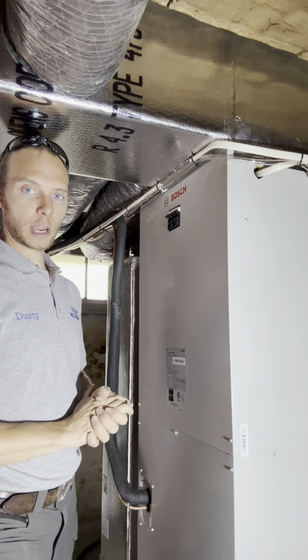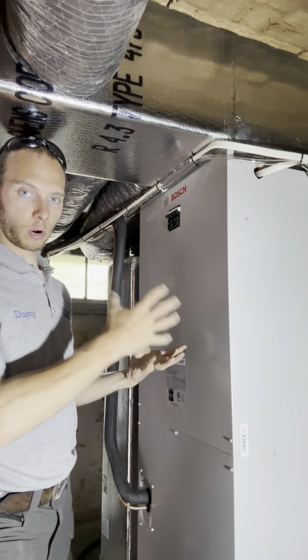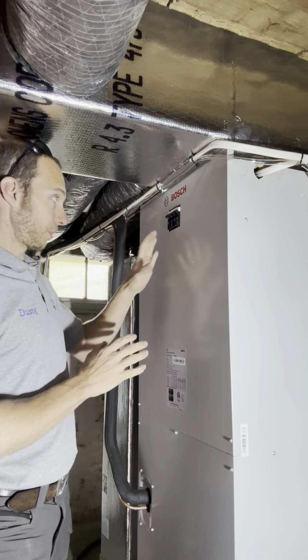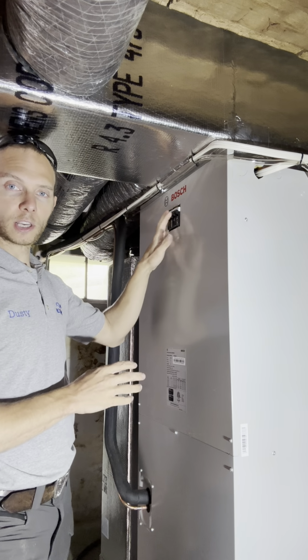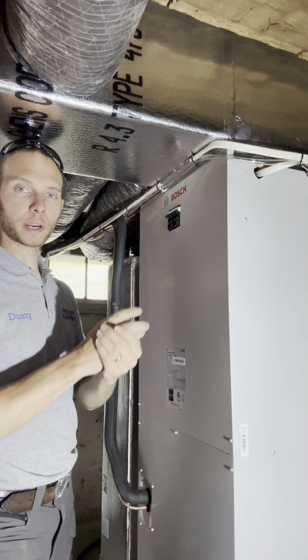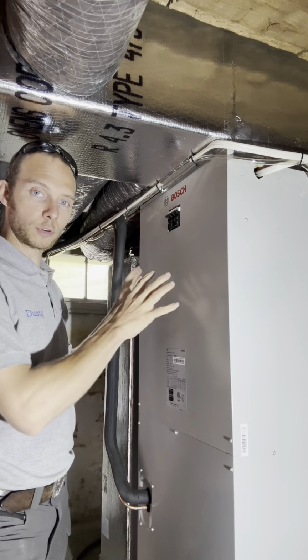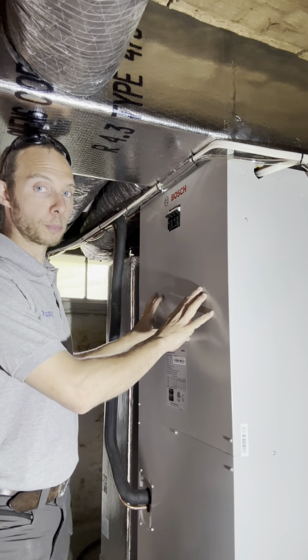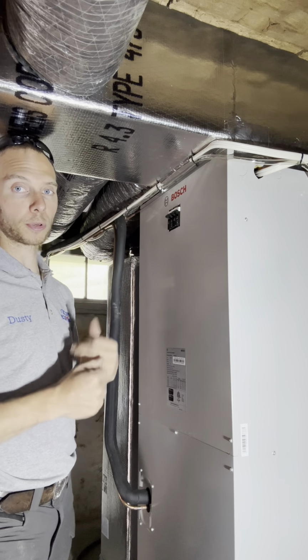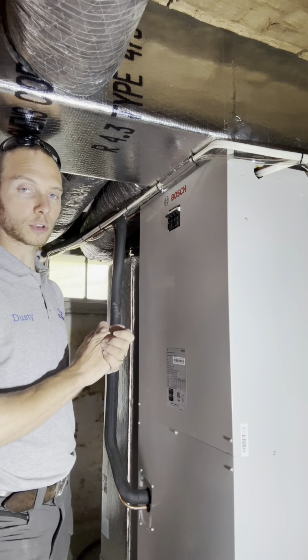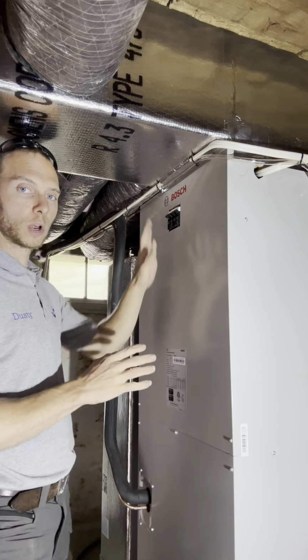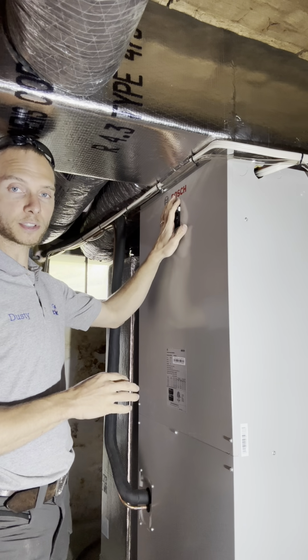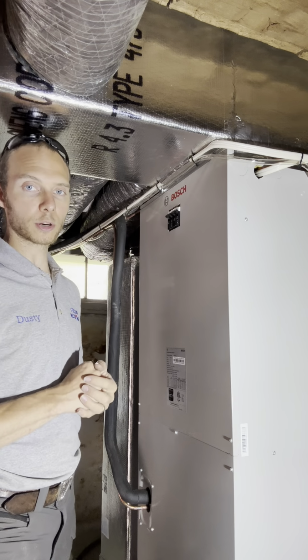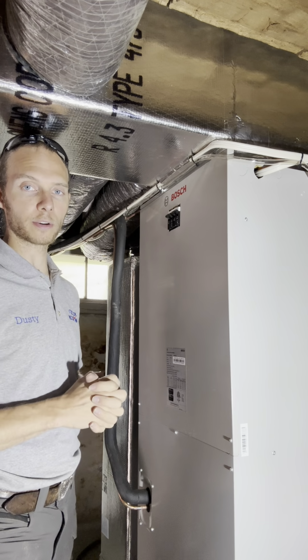There are breakers at your main electric panel that are for this. With this particular unit being a 15 kilowatt, it has two separate breakers in the panel. So if you for some reason are opening this up, make sure you turn both breakers off because there could still be power in this unit. So two breakers here just for shutoff sake, and two breakers in the electric panel for shutoff and safety sake if something gets overloaded.